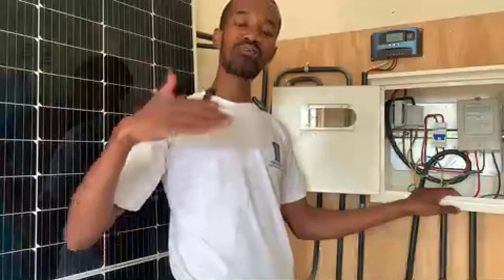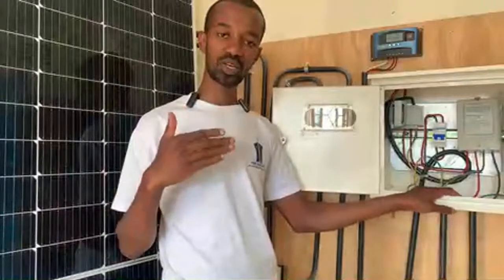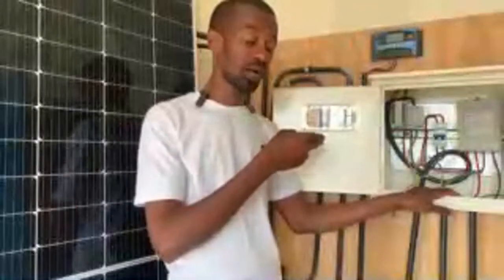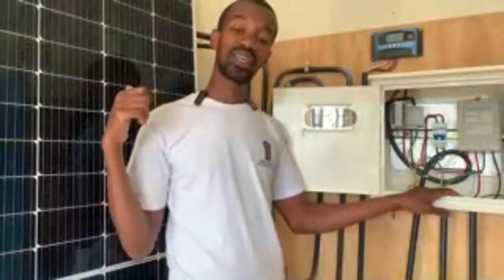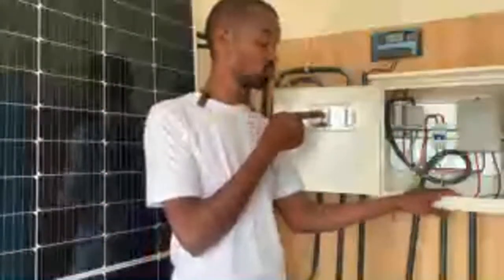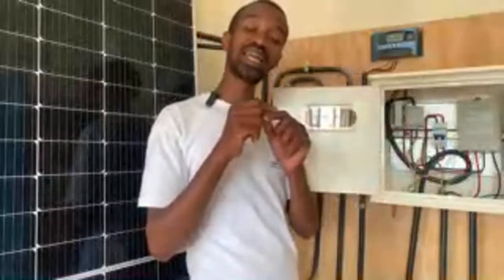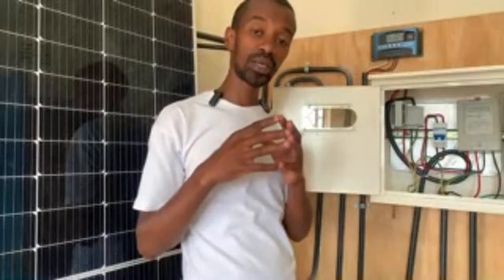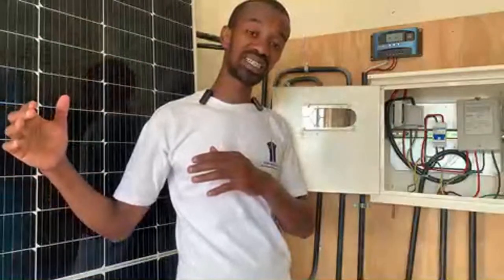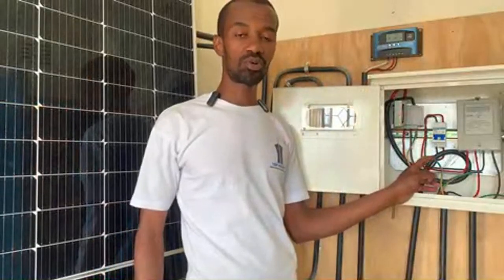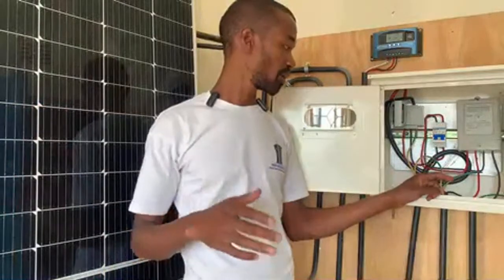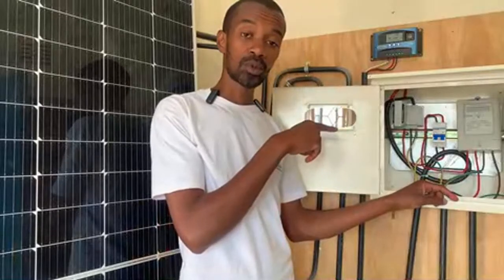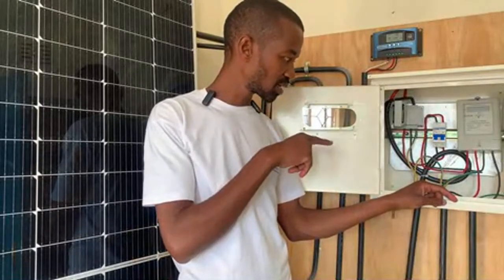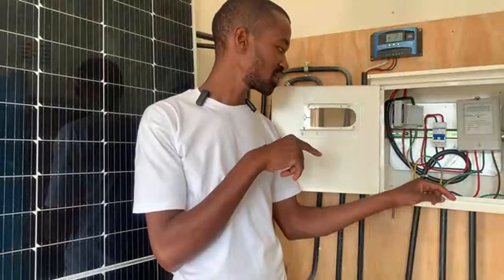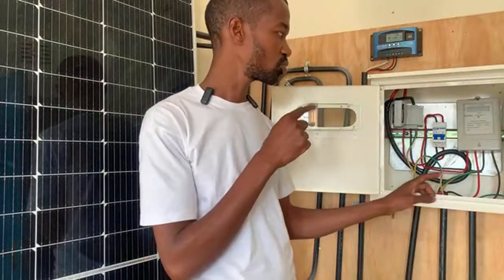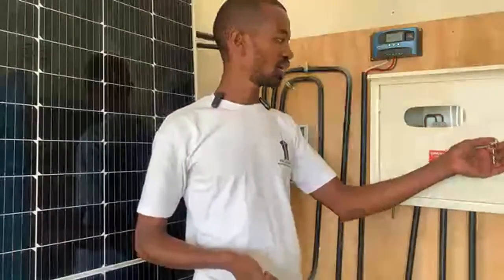If we have heating circuits in that electrical installation, the connection matters, the type of material matters, the size of the cable matters. Because if the heaters are on and running and you have a loose connection at this particular point, even though you've done everything perfect internally, from the consumer unit all the way to the specific appliance, the heater, if you compromise at the meter box level, then all the work you did is in vain. That circuit will strain whatever connection is here, causing heating at this point, arcing, and burning of the insulation of these cables.